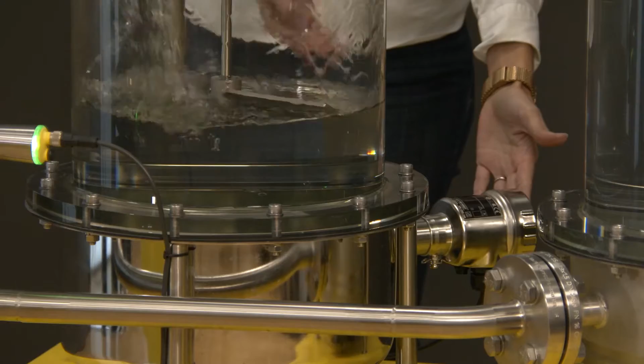Let's have a look at our demonstration unit again. Also here we have an electronic differential pressure system installed. Here above we have a pressure device which measures the overall pressure. And also on the back side there's another sensor installed at the bottom to measure the hydrostatic pressure. In that case they are just simply mounted and then connected via a normal standard cable. So here the big advantage is the easy mounting via the cable, no oil filling inside, no capillary systems, and therefore also no influence when there are temperature changes.